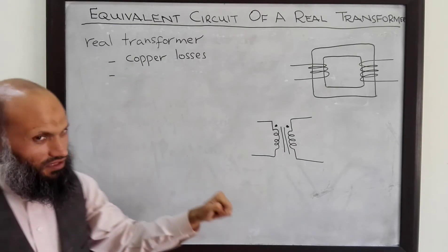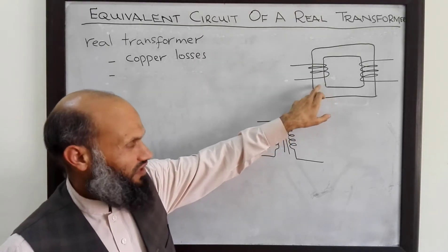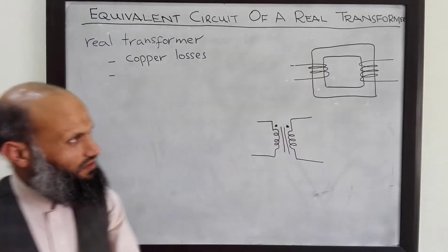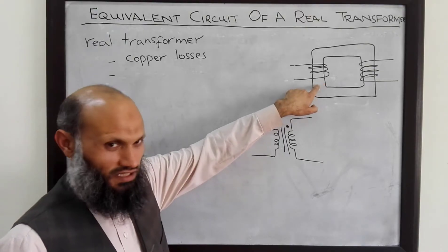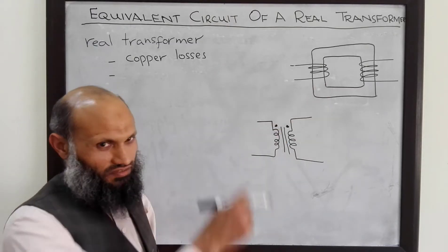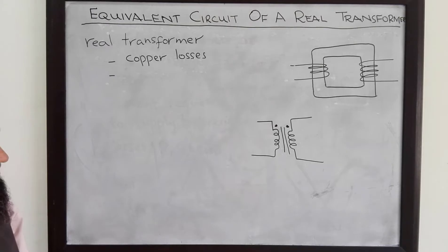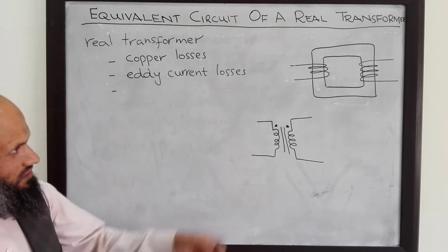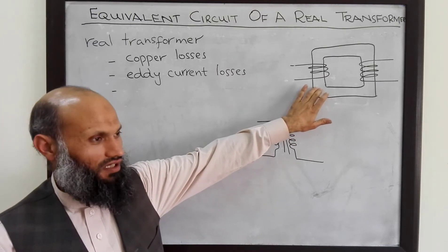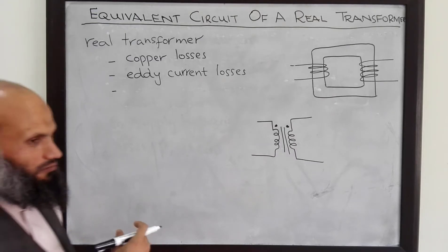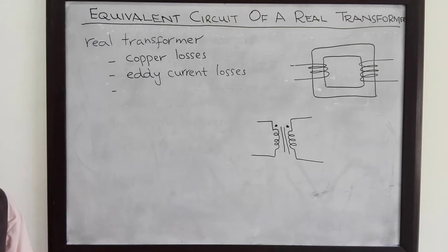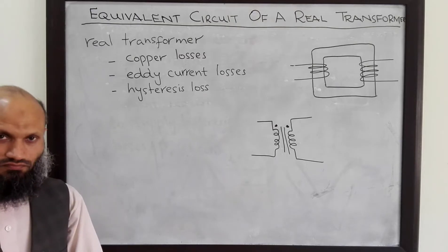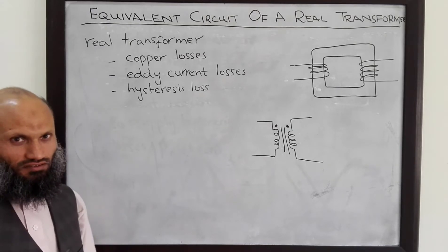Another source of power losses is eddy current losses. The changing flux which flows in the core of the transformer not only links with the primary and secondary windings but also links with the core itself. This induces a voltage in the core, causing currents to flow — these are called eddy currents — and their flow through a resistive path results in losses. Furthermore, there are hysteresis losses in ferromagnetic materials, where domains align and disalign with the magnetic field, resulting in energy loss proportional to the area of the hysteresis loop.